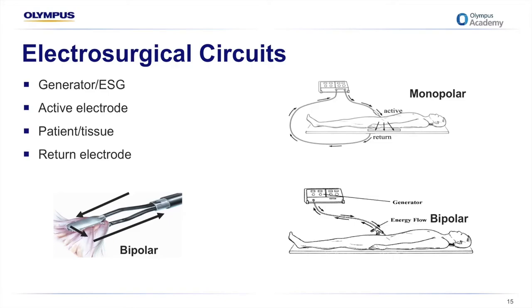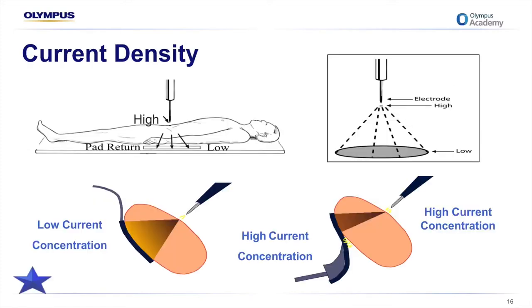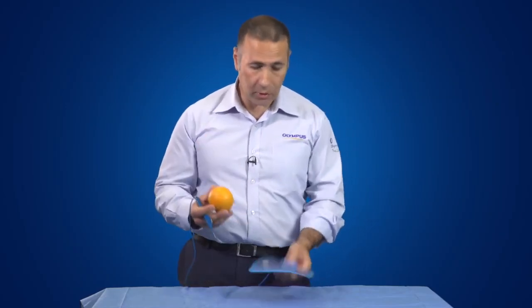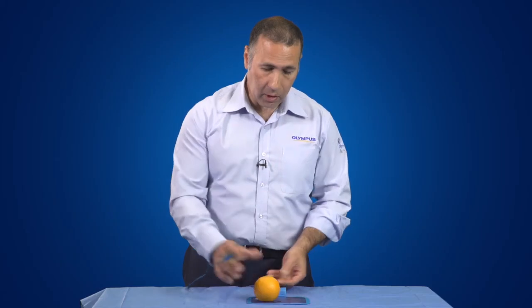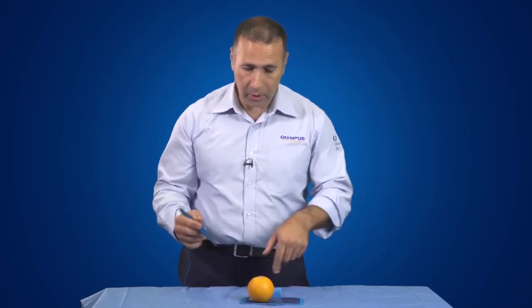Another question I'll ask is, what's the difference between monopolar and bipolar technology? And the answer is simply, once again, the location of that return electrode and also the size and shape. So to further consolidate that and give you a better understanding of current density, I'll now give you a demonstration of how the size and shape of the electrode can affect the current density. So in order to demonstrate current density to you, I'm going to show you this orange on the return electrode plate. So here we've got good contact, it's got a complete circuit.